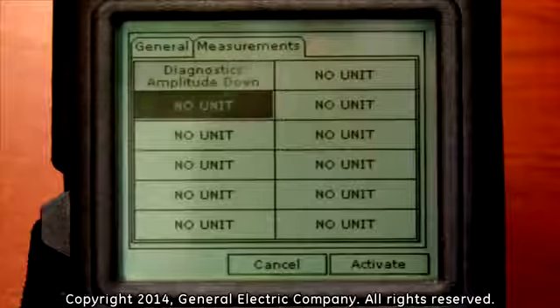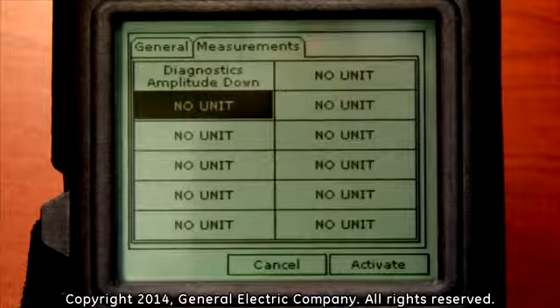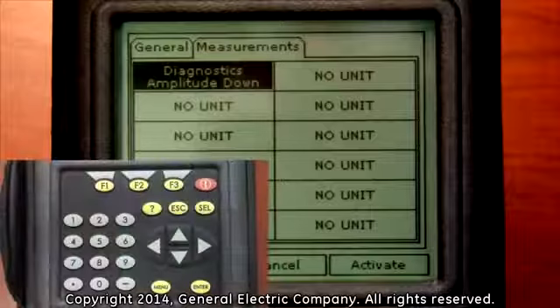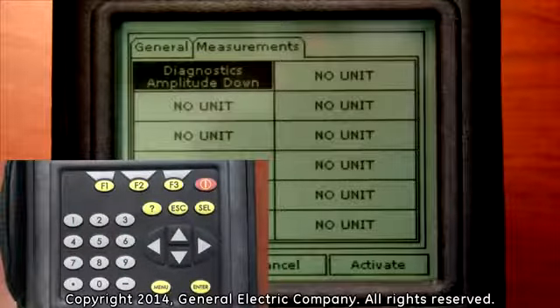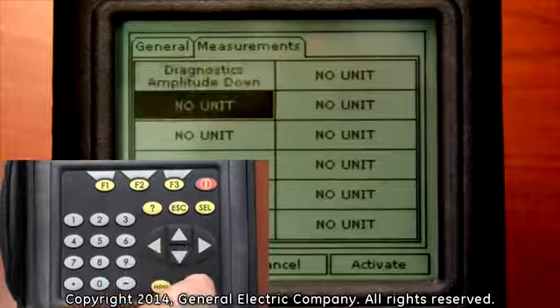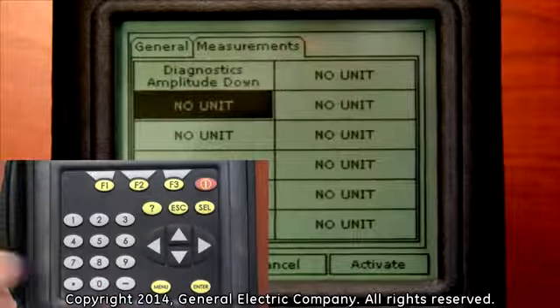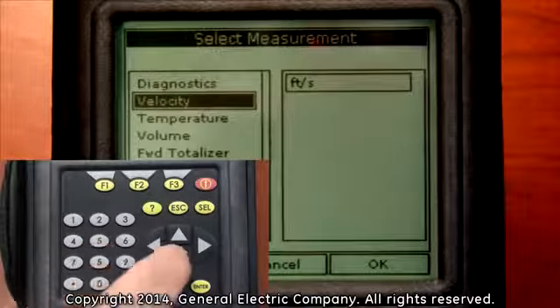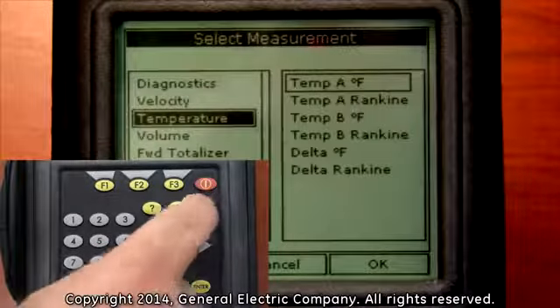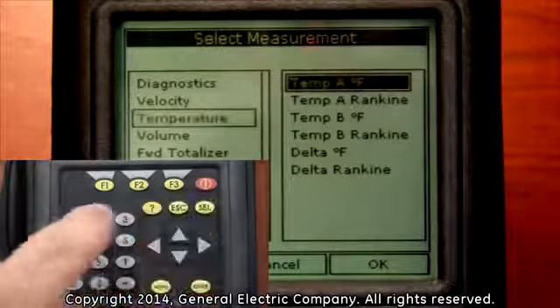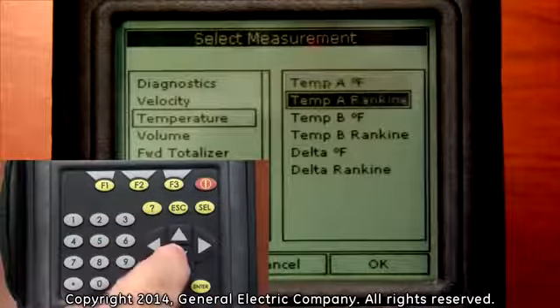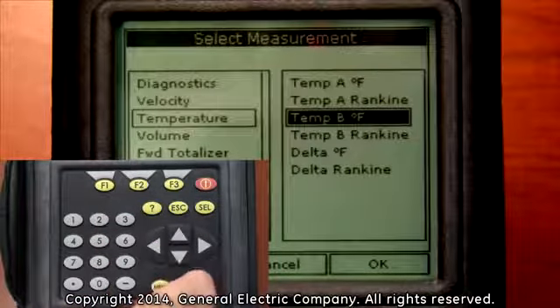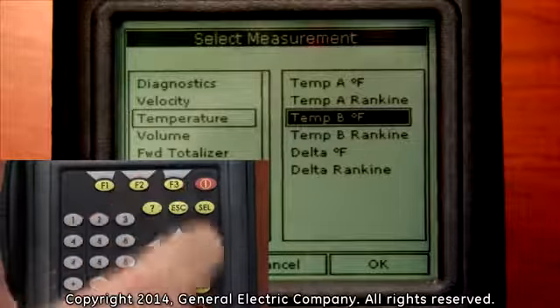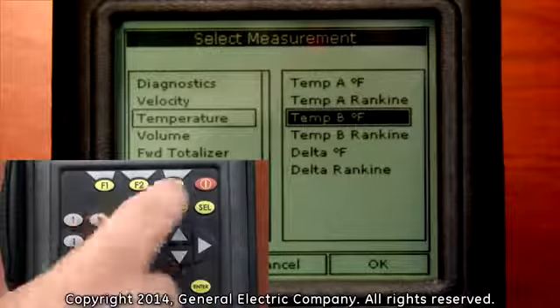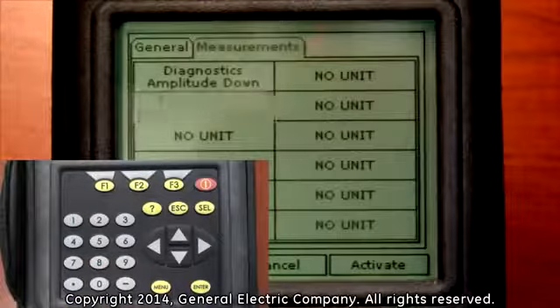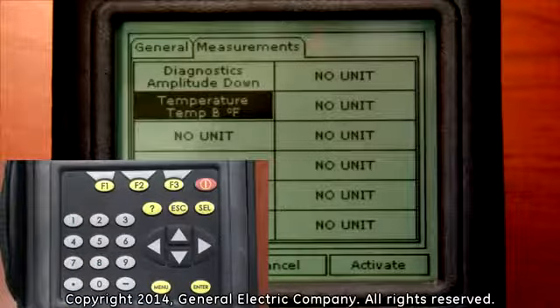Repeat this procedure for the number of measurements you would like to take for this log. For example, press the down arrow key to select the next No Unit field and press the Enter button on the keypad. Use the down arrow key on the keypad to highlight the temperature measurement. Now press the Select button on the keypad. Use the down arrow key on the keypad to navigate down and highlight the Temperature B degrees Fahrenheit option. Press the Enter key to set the option and then press the F3 key, which corresponds to the OK selection on the bottom right hand of the display screen.